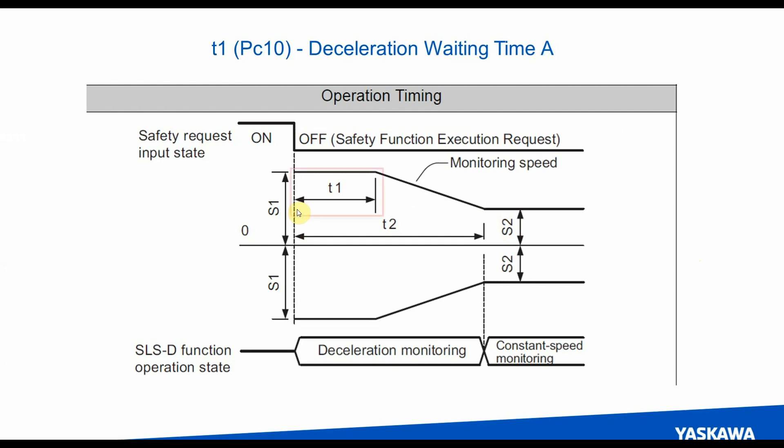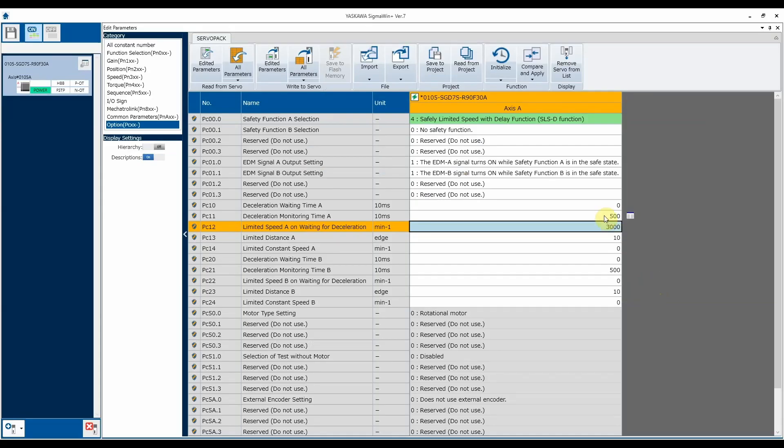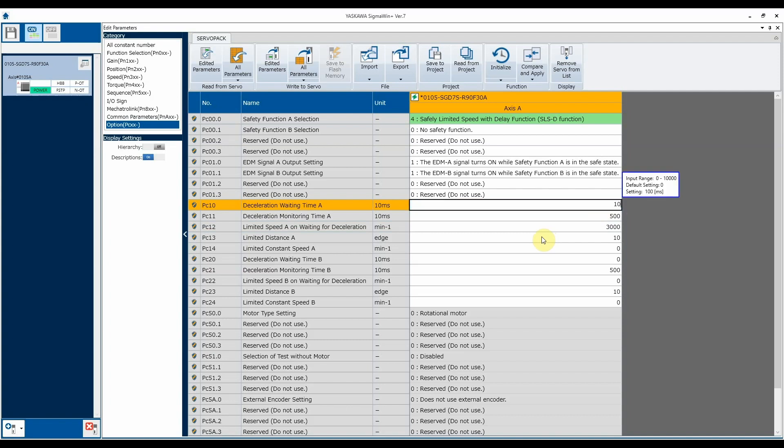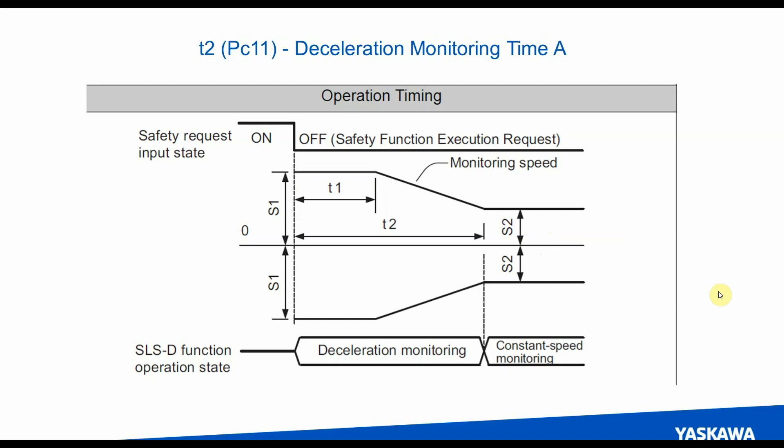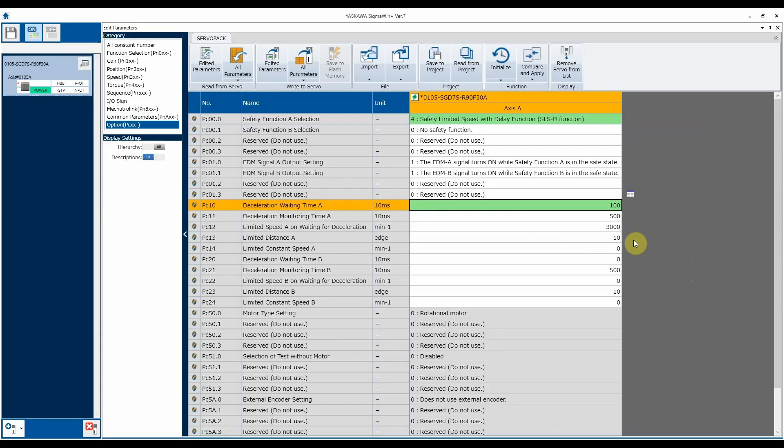The next one's going to be the time in which the motor needs to start decelerating. That is set to zero by default. Just to give us a little bit of time here, just to show implementation, we'll make it 100. And note the units are in tens of milliseconds. So value of 100 is equal to one second. The next time is going to be the time in which we need to be at a safe limited speed. That's T2. That by default is 500 or 5 seconds. We'll leave that alone for right now.